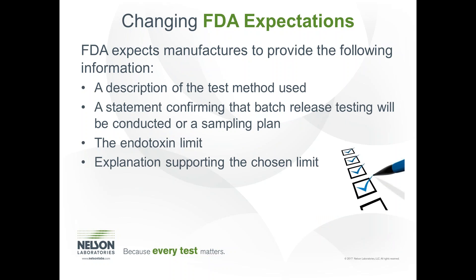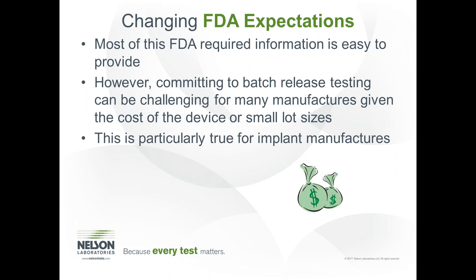For 510(k) submissions, FDA now requires medical device manufacturers, including implant manufacturers, to provide four key points: a description of the test method used, a statement confirming that batch release testing will be conducted or a sampling plan, the endotoxin limit, and an explanation supporting that chosen limit. Most of this information is quite straightforward. However, committing to batch release testing can be very challenging because of the cost of medical devices or small lot sizes. This is particularly true for implant manufacturers, where lot sizes can be as little as one for custom-made implants.